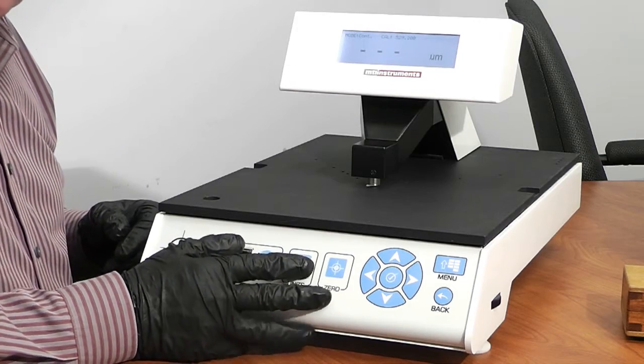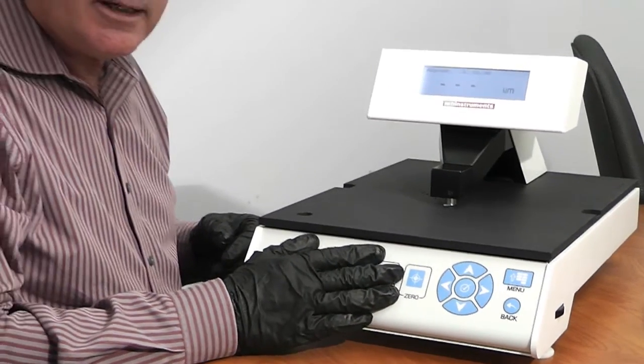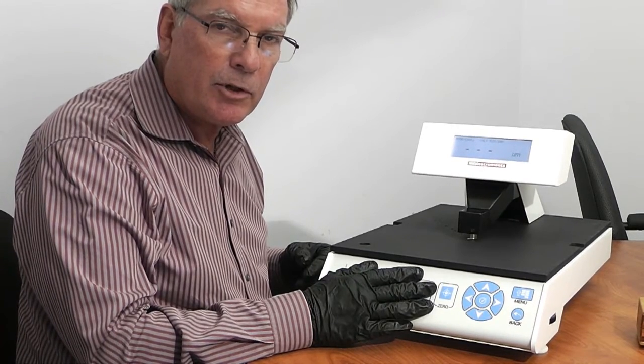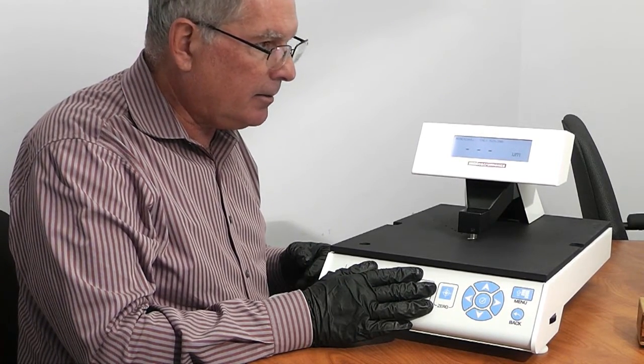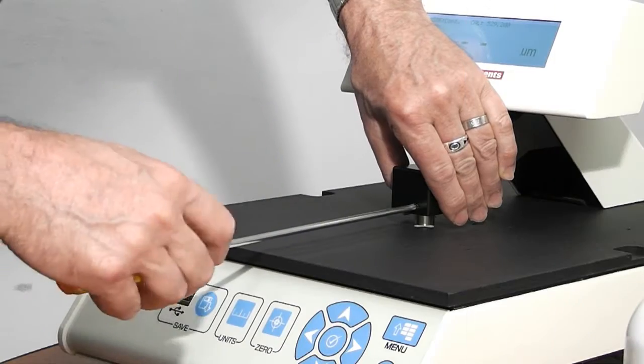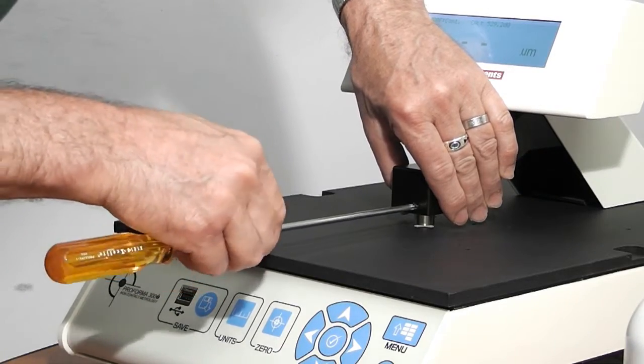The Proforma 300i can also measure semi-insulating or semi-conducting materials, such as gallium arsenide, high bulk resistivity, indium gallium phosphide, and other such exotic materials. In order to do that, what we have to do is take off this nose piece right here.